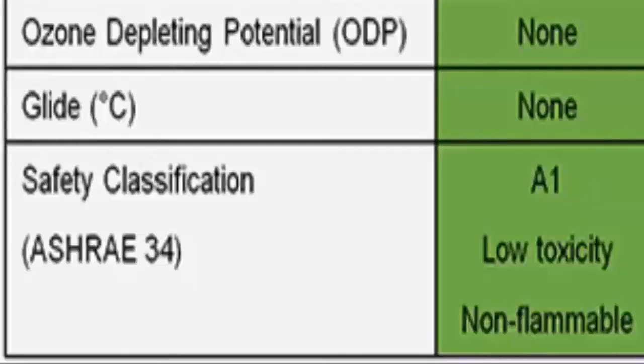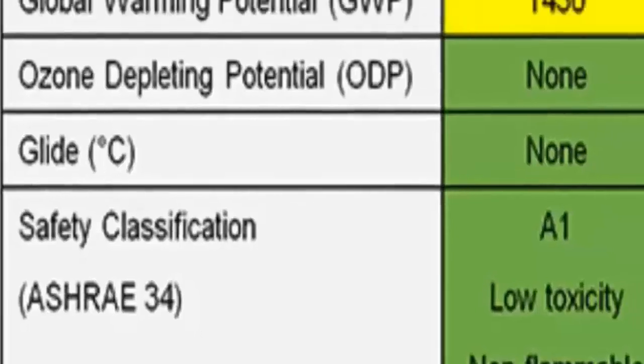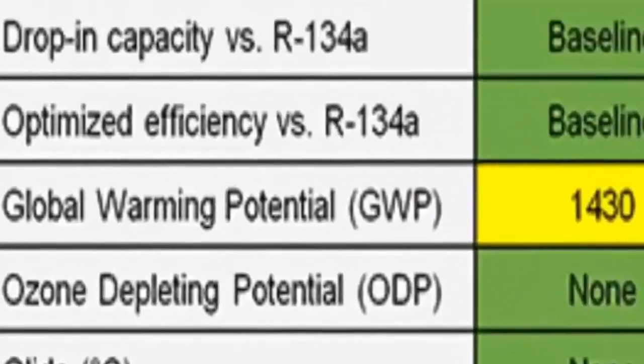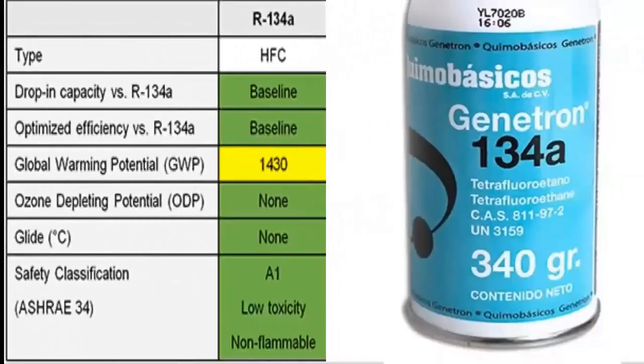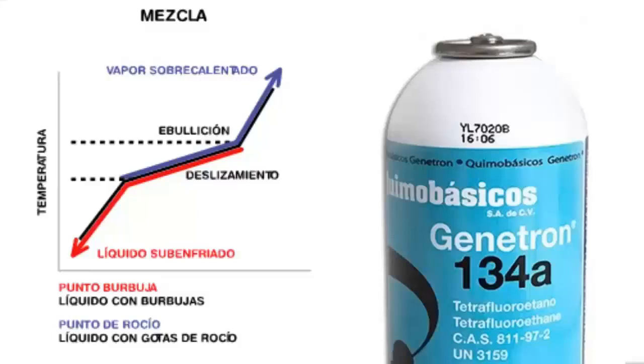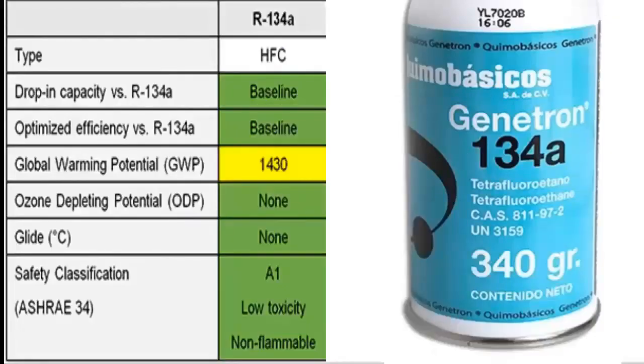4. R-134A refrigerant gas has a global warming potential of 1430. 5. R-134A refrigerant has no glide. This means that its temperature remains constant during the phase change, as long as the pressure does not change. 6. R-134A has great stability and compatibility with most materials.